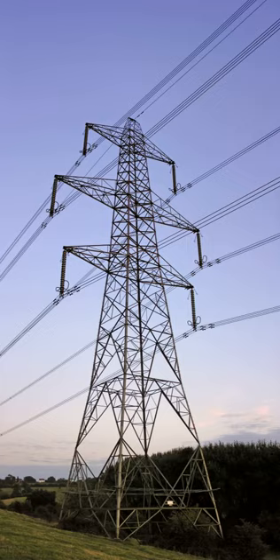Generally, three conductors are required per AC three-phase circuit, although single-phase and DC circuits are also carried on towers. Conductors may be arranged in one plane, or by use of several cross arms may be arranged in a roughly symmetrical, triangulated pattern to balance the impedances of all three phases.